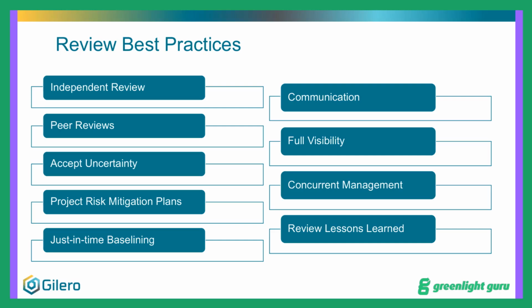How do we do design review right then? Independent review is a required element of 21 CFR 820, and at least one member of the review team must not have direct responsibility for the design stage being reviewed. By selecting a knowledgeable, critical, independent reviewer, the design review is more likely to detect any issues with the product or design process. Peer reviews means grabbing specialists who are knowledgeable in the subject matter being reviewed, who may or may not be your designated independent reviewer.